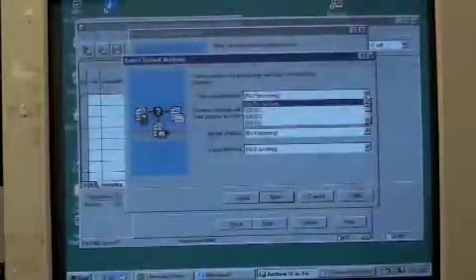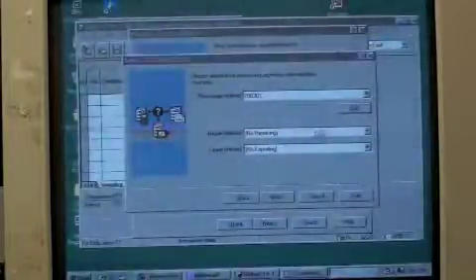Processing method — this is the method by which the results will actually be processed. We'll choose a previous one and edit it. The processing method is where, when the chromatography comes out, you have the opportunity to indicate what each peak is by its name. As you can see in this previously built example: uracil has a retention time of two minutes, caffeine three minutes, aspirin four minutes. These are approximate values which can be changed later during the integration process.